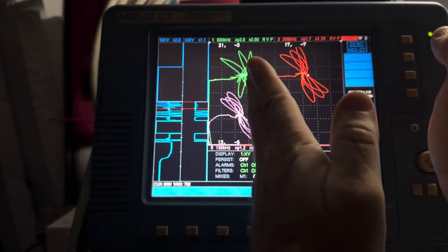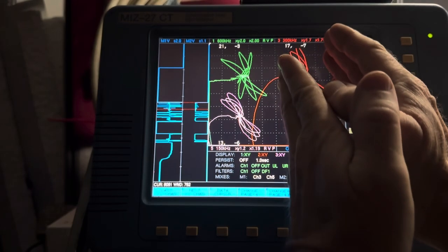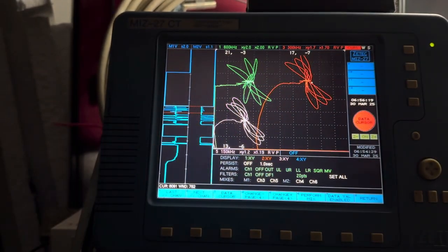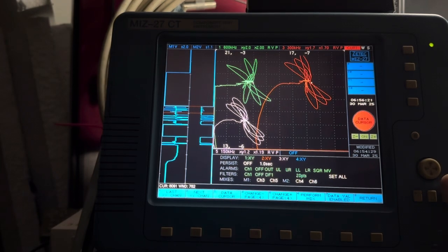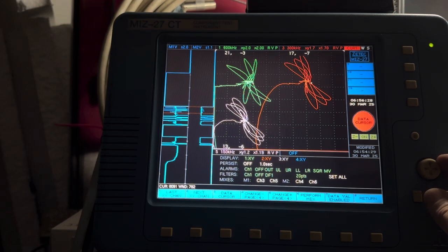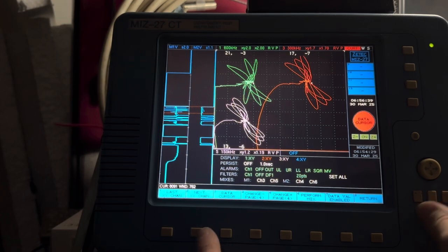But we've got a certain amount of phase spread on the highest frequency, 600 kilohertz. Then we've got less phase spread with 300 kilohertz. And the least phase spread of all three of these channels is the 150 kilohertz. It's more penetrating. It can see farther out. It's good for locating tube supports because they're far away from the test coil. But you have less phase spread, so it's not as accurate when you're trying to size flaws based on their phase. So now we know that we look at phase rotation a whole lot in data evaluation.